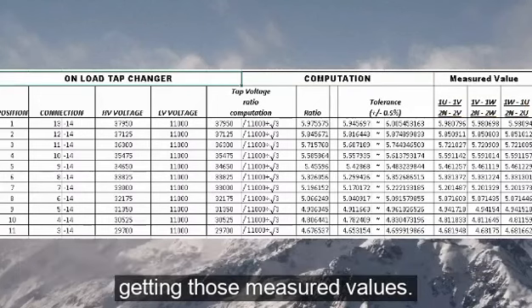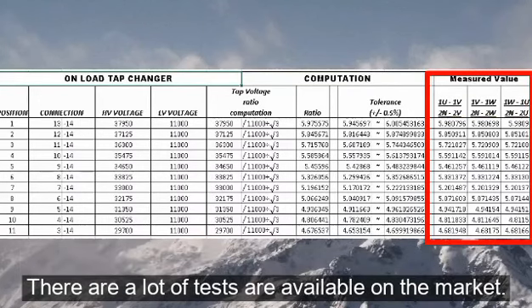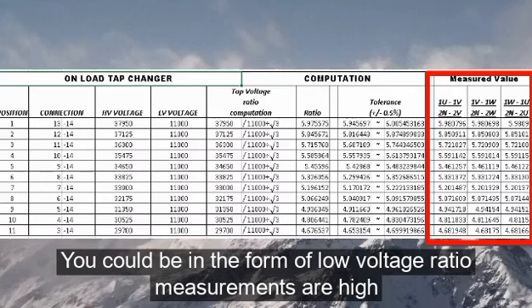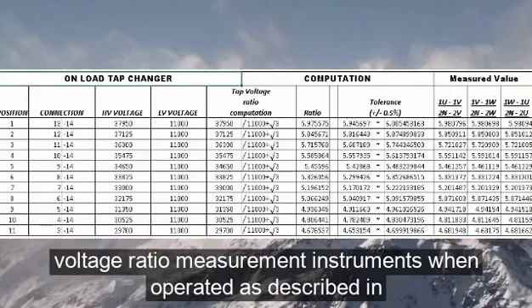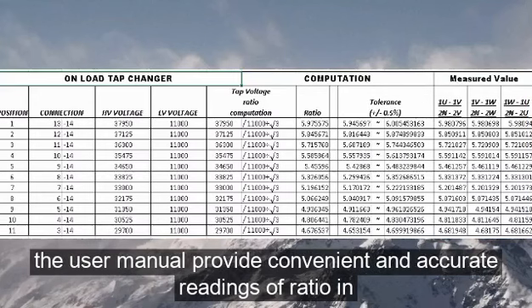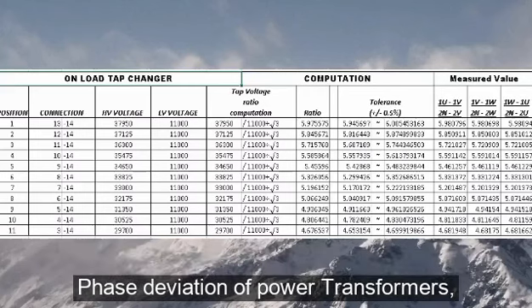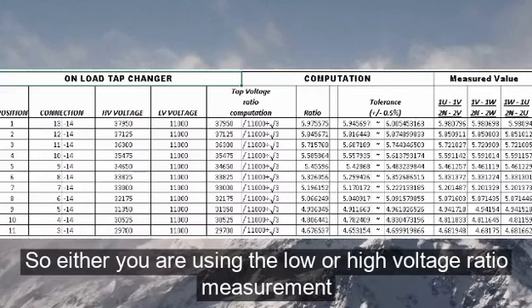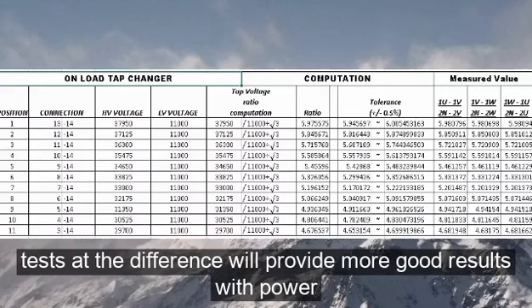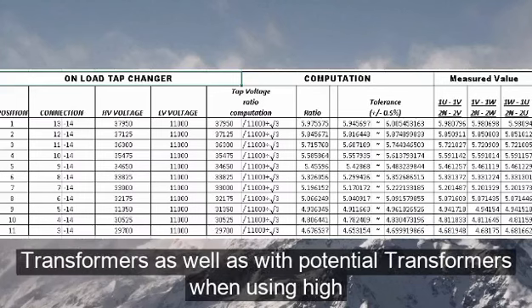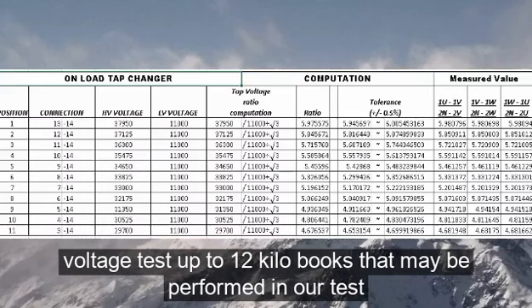In getting those measured values, there are a lot of test sets available on the market. It could be in the form of low voltage ratio measurement or high voltage ratio measurement. The instruments, when operated as described in the user manual, provide convenient and accurate readings of ratio and phase deviation of power transformers. Either you are using the low or high voltage ratio measurement test set, the difference will provide good results with power transformers as well as with potential transformers, when using higher voltage tests up to 12 kV that may be performed.